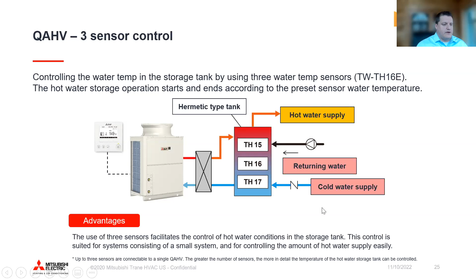The heat pump's going to run again, provide as much heat as it can at whatever set point you put it to. And then it's going to run all the way down until your TH17 value gets to a predefined number. So that might be 135, 140, right? So these sensors can be placed in any tanks, but typically this TH17 sensor is always closest to the coldest water coming into the system. And then your TH15 and 16 can be spread across tanks as need be.